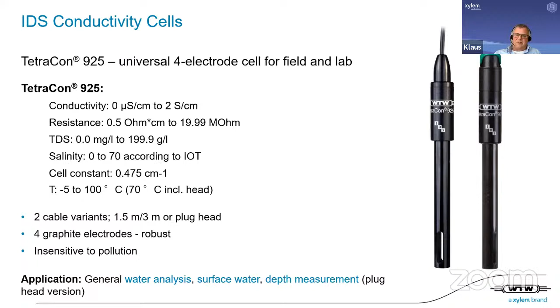electroplating bath or something, we have a special edition, because for such applications, it's good to have a head which is made of PEEK. PEEK is extremely resistant against acids. If you are using this in an industrial context, then order the Tetracon 925C. It has the same properties as the Tetracon 925, but the head is much more stable against chemical attack.